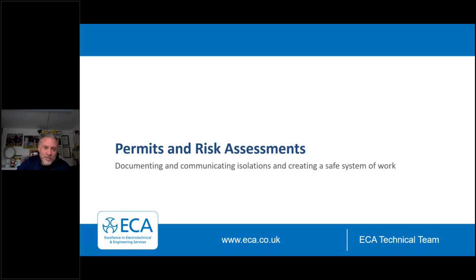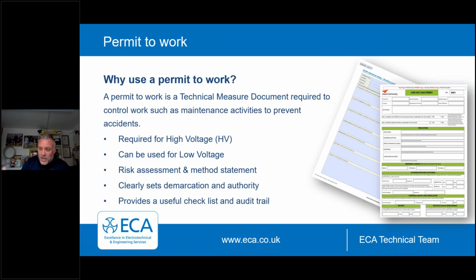This leads us nicely on to documenting - permits and risk assessments. Especially where there are a lot of circuits to lock off, or in industrial and commercial enterprises, it's a good idea to use a permit to work. It's a technical measure document required to control work such as maintenance activities to prevent accidents. It's definitely a requirement for high voltage, and can be used on low voltage. It's a great way of introducing a risk assessment and method statement. Importantly, it clearly demarcates authority - effectively handing the circuit over in a safe manner - and provides a useful checklist and audit trail.